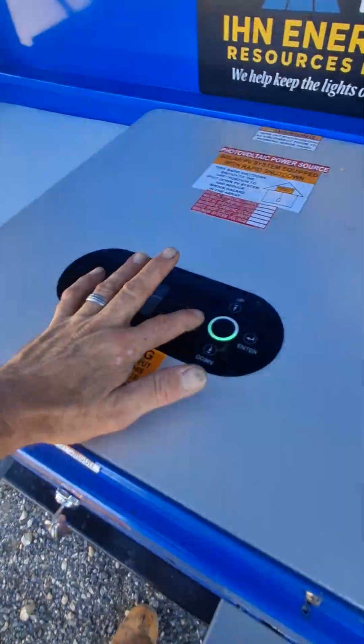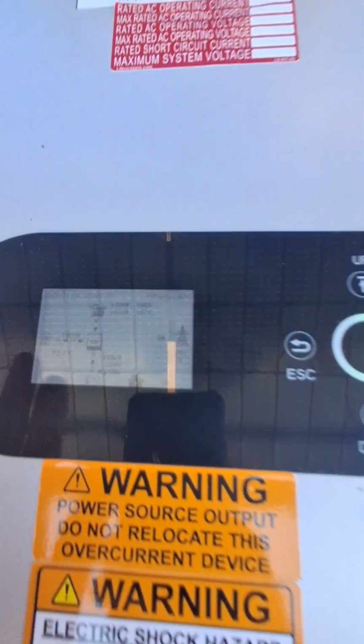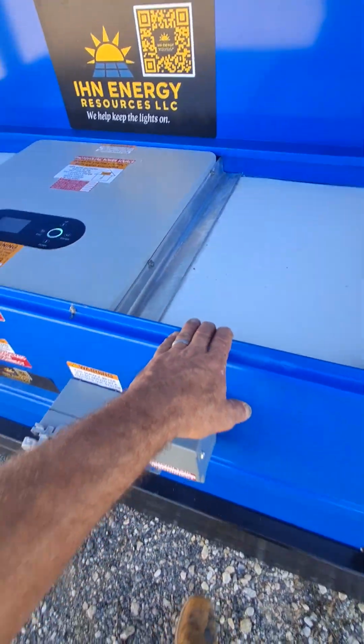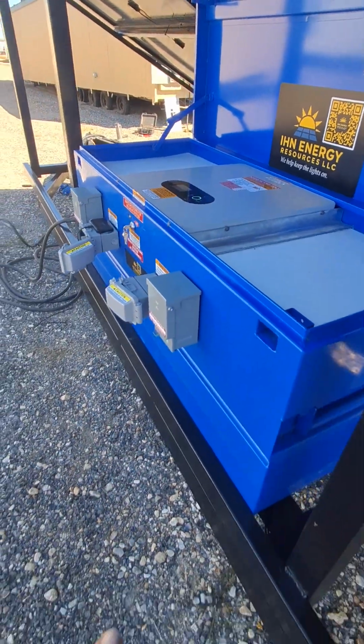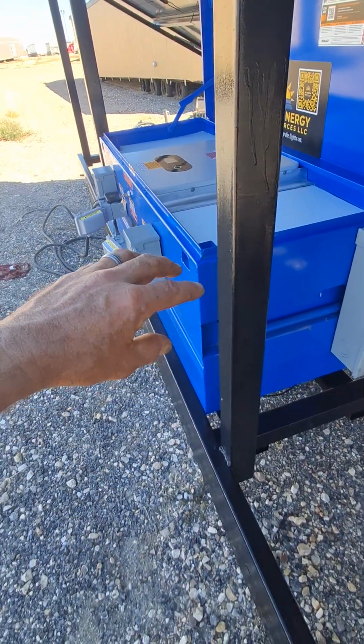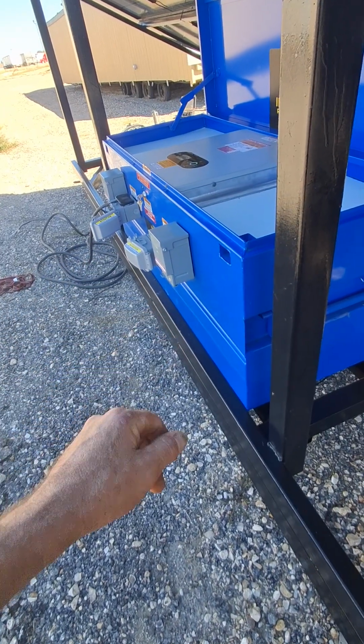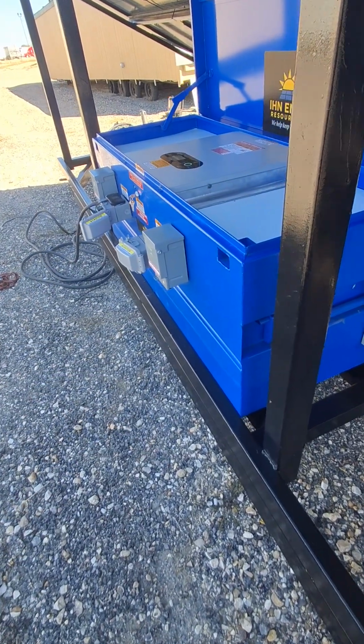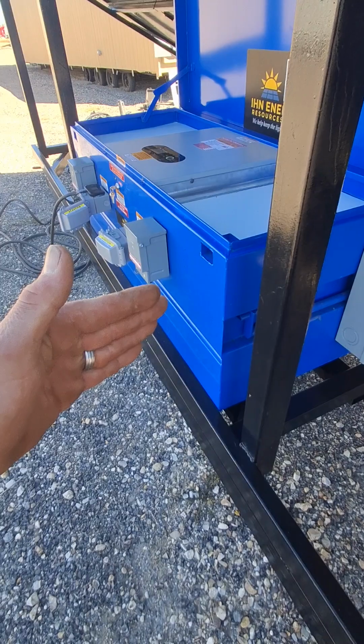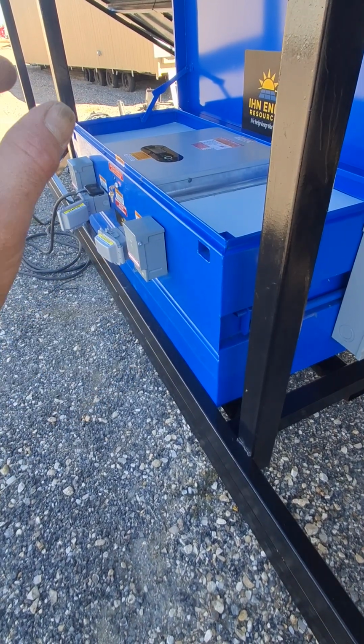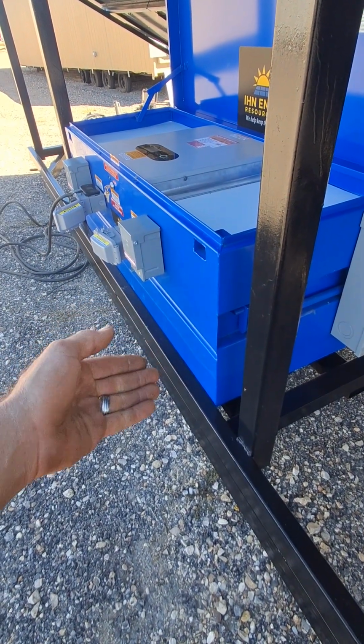Now, what makes this unique is, besides Wi-Fi communication and all that other jazz, I actually have a BMS communicating factor that can tell me if I show up on this job and we're having an issue with a particular battery bank—it will tell me that it's pack number 2 and it's cell number 6. So I'm able to go ahead and retrofit out that cell while it's still in operation, pull it out, put the new one in, and put it back online.